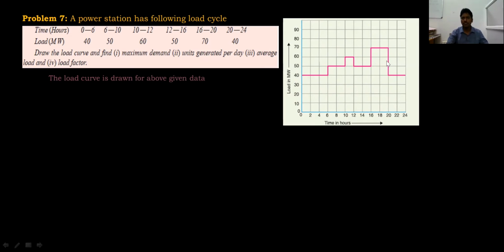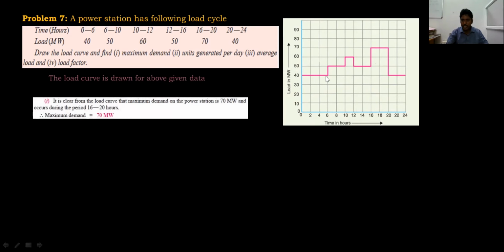Therefore, the maximum demand of the station is always the peak point of the load curve. Here the peak point of the load curve is this one, so it is 70 megawatts. The second question is units generated per day, which is the area under the load curve. I need to find this area, so I am dividing it into subparts and adding all those areas, which gives the area under the load curve.